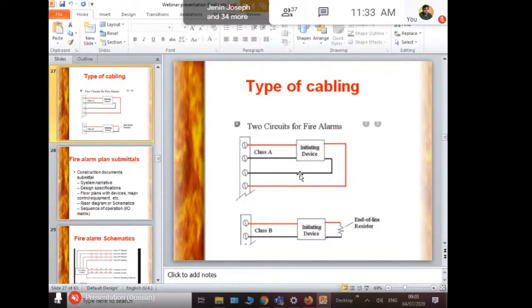Okay, and this is a class B wiring. So what is a class B wiring? We'll go to the device and we'll close it with the end of line resistor. Why do we put an end of line resistor? Otherwise it will show an open circuit, or it will show a return voltage. So either of it will show. So to avoid it, we'll close it with the end of line resistor.